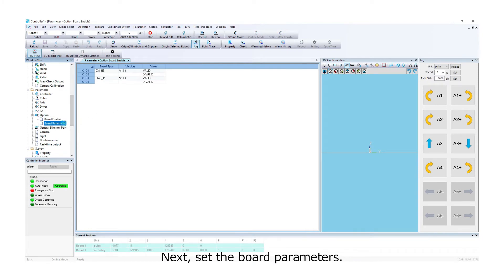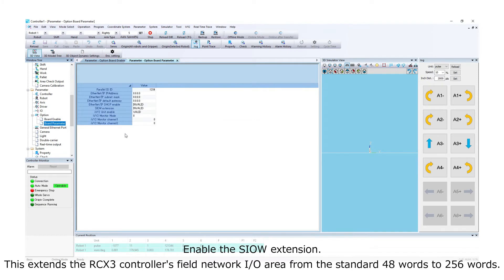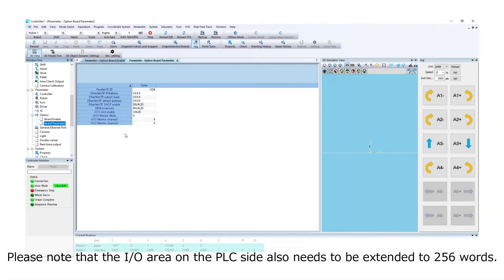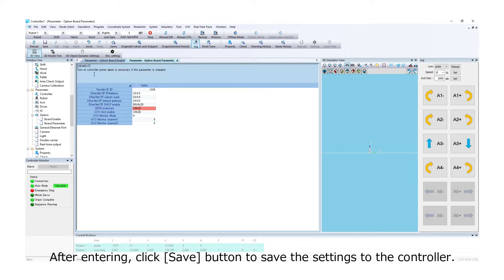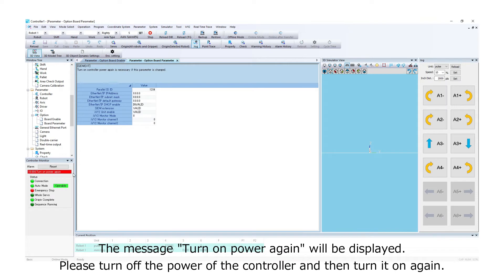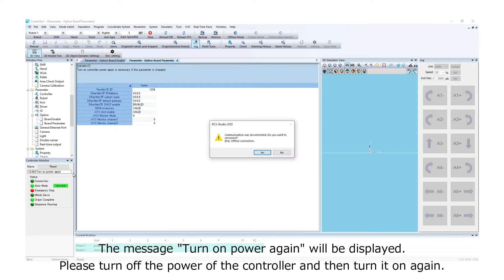Next, set the board parameters. Enable the SIOW extension. This extends the RCX3 controller's field network input and output area from the standard 48 words to 256 words. Please note that the input and output area on the PLC side also needs to be extended to 256 words. After entering, click the Save button to save the settings to the controller. The message 'turn on power again' will be displayed, so please turn off the power of the controller and then turn it on again.